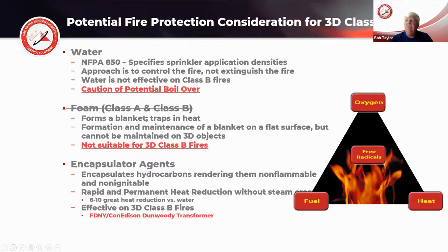So again, as we talked about three-dimensional fires, NFPA 850, excuse me, is a recommended practice for the electric power generation sector. It gives some specific sprinkler design densities. It recognizes that water may not be the most effective on it. It cautions people over boil over, where you get the water and the oil, and the water heats up and starts to boil and accelerates the spilling or the release of the combustible liquid fire. We know foam traps in heat. It's not a great cooling capability. It's difficult to maintain a blanket on, and it just doesn't work on three-dimensional fires at all.